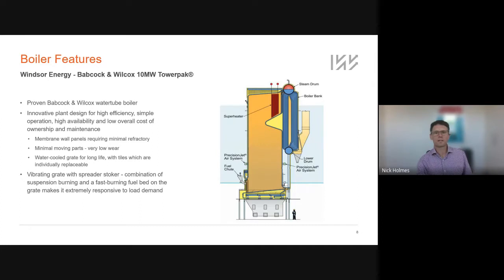One of the big drivers here was allowing the boiler to burn very high moisture content fuel. I think the other boilers on site were struggling. One was designed specifically just to burn bark. So this had some additional features to preheat the combustion air to quite a high temperature to allow that fuel to be burnt.